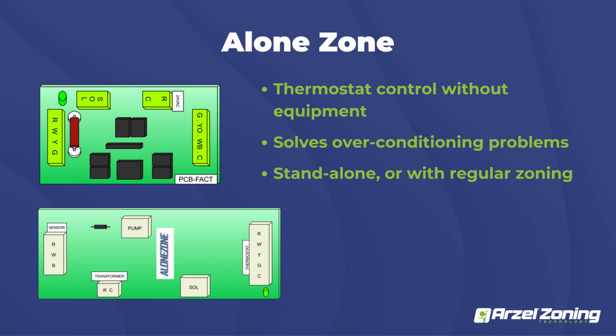We also have a couple of different boards that we offer that can either be standalone components or they can be built into any of the panels that we offer as well. The first one on the top there, the PCB Fact, that's our Fact board. It has really two basic uses, one of them being an alone zone or kind of like a slave zone, if you guys are familiar. It'll give you guys damper operation on a zone that's controlled still from a thermostat, but it would restrict that zone from being able to actually physically kick on your HVAC equipment. So if you had a smaller zone in a home, it can't really be its own zone. You can incorporate it with the Fact board.